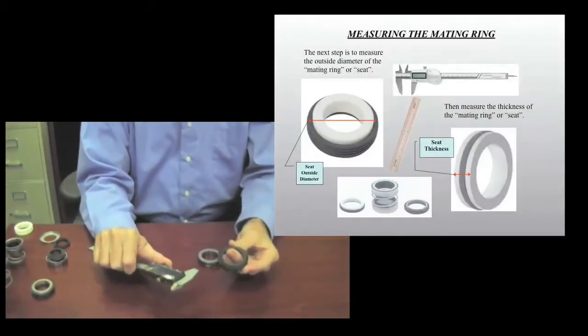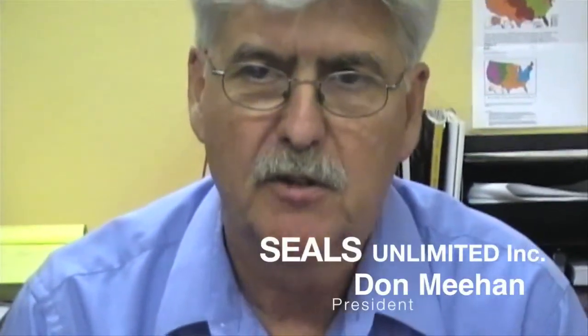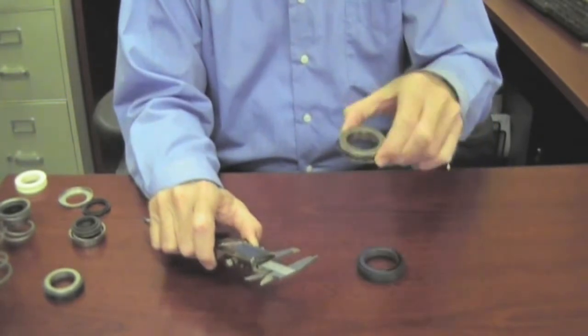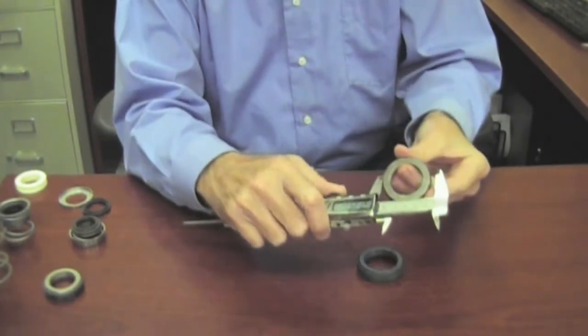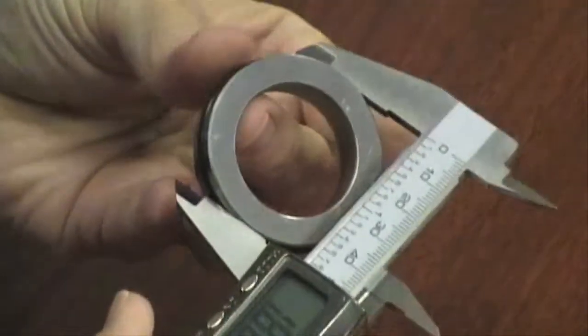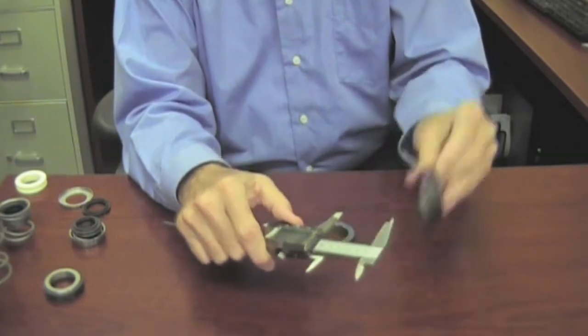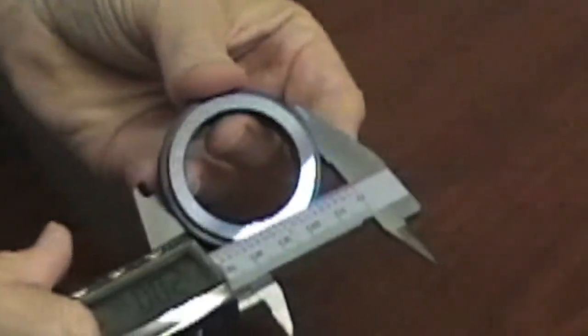The next critical dimension we need for the mechanical seal is the outside diameter of the seat. This is your seat. There is another type of seat. We are looking for this dimension out here, which is the outside diameter of the seat. Here it is on one that has a rubber cup on it instead of an o-ring.